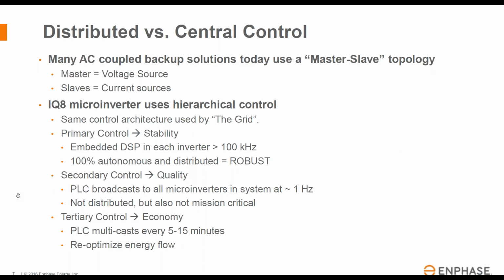And then we rely on tertiary control, which is a third level of control. And we view that primarily as an economic optimization of the system. And the power line carrier would update that about every 5 to 15 minutes. And that will optimize the energy flow primarily based on economic drivers, but it could also be based on commands or requests from external, from the utility company, for example, from the microgrid operator, from any external event, which could essentially override the economic optimization to use those assets for other purposes.